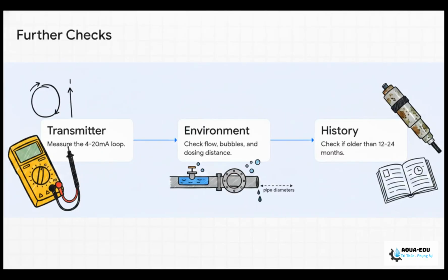Let's wrap up this diagnosis. Step 5. Grab a multimeter and measure that 4 to 20 milliamp loop, just to be totally sure the transmitter itself isn't the problem. Step 6 is all about the environment. Look around. Is the probe installed way too close to the chemical dosing point? The manual strictly states it needs to be at least 10 to 20 pipe diameters away just to ensure proper mixing. Are there air bubbles blocking the glass?